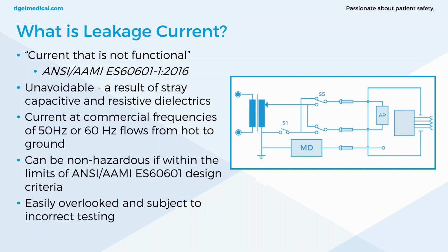The earth and enclosure type, the ground and enclosure type leakage currents have limits that reflect the values of macro shock. So the risk to the user or clinician, the visitor, the limits are higher because, from the previous slides, macro shock had higher levels of current before ventricular fibrillation occurs. Now, from the micro shock slide, we know that medical electrical equipment is designed to have high levels of isolation due to applied parts and the risks of micro shock. And that's why the limits for the applied parts are much lower and there's higher degrees of isolation.